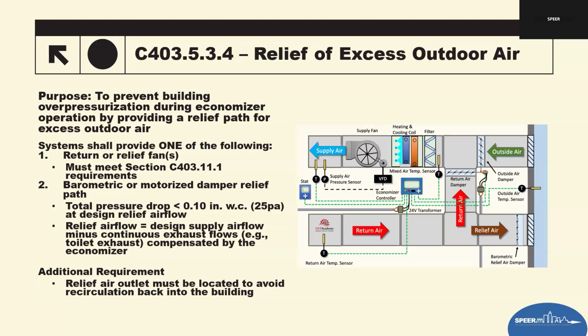And for field inspection tips, observe economizer operation and verify the relief path opens as intended. And then check that the relief outlet is not located near the opening for the intakes. And then confirm return relief fans operate accordingly with the economizer position.